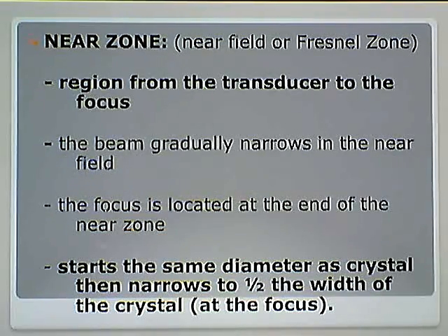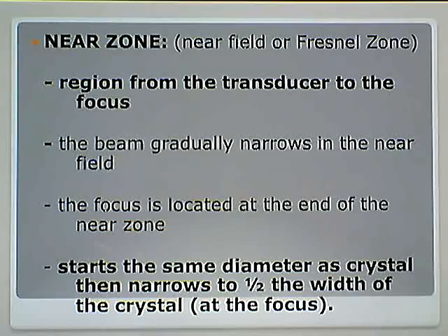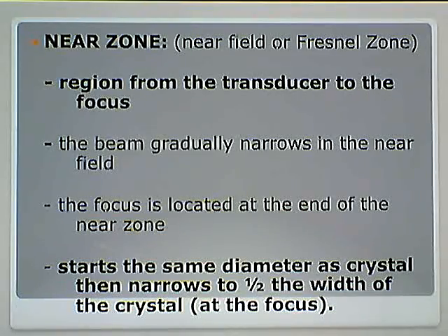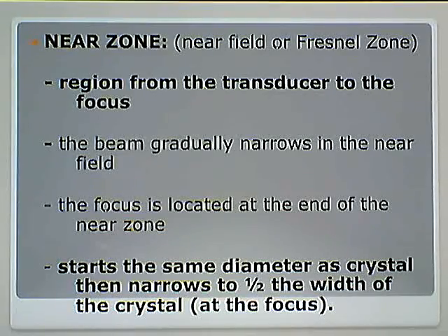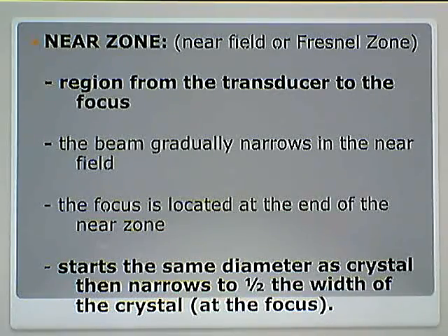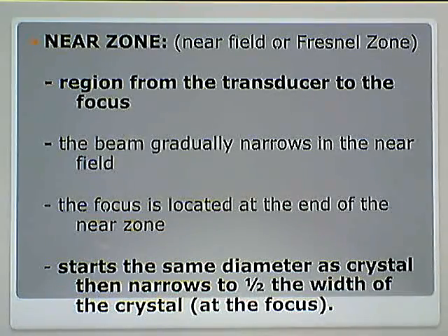The near zone, or near field, or Fresnel zone, is the region from the transducer to the focus — from the start of the beam all the way to the end of the narrowing. The beam gradually narrows through the near field. The focus is located at the end of the near zone. What's the start of the near zone? The transducer. What's the end of the near zone? The focus.